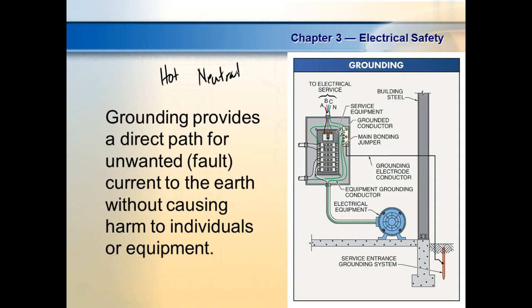Now, the problem we have is that anytime I push electromagnetic waves through a chunk of metal, it's going to induce voltage into it. Y'all know that, right? We proved that over here. So 90% of our current is probably in transmission. It's AC. So if I've got a metal cabinet and I've got AC inside of it, if I didn't do something, it would build up a charge automatically relative to ground. So that means you'd walk up on it and you'd touch it and it would shock. So what they do is everything metal has to be connected to ground. So if something is connected to earth ground, that is the common for almost all AC being generated, then there's no way in the world that metal chassis could pick up a static voltage, right, or a static charge.